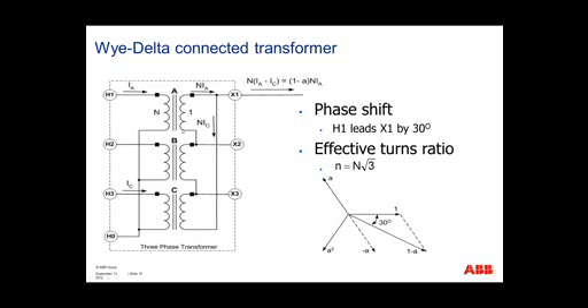For a Wye-Delta connected transformer, this is what the connections are going to look like. The high side is Y connected, just like a Wye-Wye, H1 connected to the polarity mark of winding A, H2 connected to the polarity mark of winding B, and H3 connected to the polarity mark of winding C. However, on the Delta connected side, if you notice, X1 is connected to the polarity mark of winding A and the non-polarity mark of winding C. X2 is connected to the polarity mark of winding B and the non-polarity mark of winding A, and X3 is connected to the polarity mark of winding C and the non-polarity mark of B. This is in turn called an A minus C delta connection.